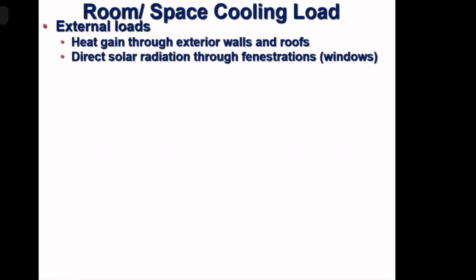Now space cooling load. Next. We said there are external loads, loads which are coming from the external sources. There are internal generation of heat. So what are the external heat? Heat gained through exterior walls or roofs, direct solar radiation through windows. That means the direct sun which enters the room through the window. Sun cannot enter through exterior walls. It only makes the exterior wall hot, and that hot wall radiates inside. But the glass window, if it is there, a portion of the heat directly comes in the room through the sun directly coming in the room through the window. Additionally, the window also gets hot and radiates it inside the room. So glass windows have a double effect, and the walls or roof have a single effect.